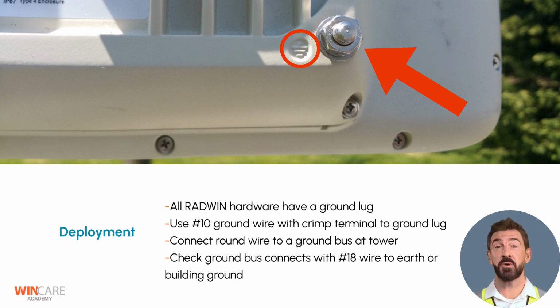Always use a number 10 ground wire with a crimp terminal to connect to the ground lug. Then, attach the ground wire securely to the site's main ground bus. Verify that the ground bus itself is bonded to earth or building ground using a number 18 AWG wire. Proper grounding through the ground lug is mandatory in every installation. It protects the equipment, ensures operational reliability, and helps maintain compliance with safety standards.